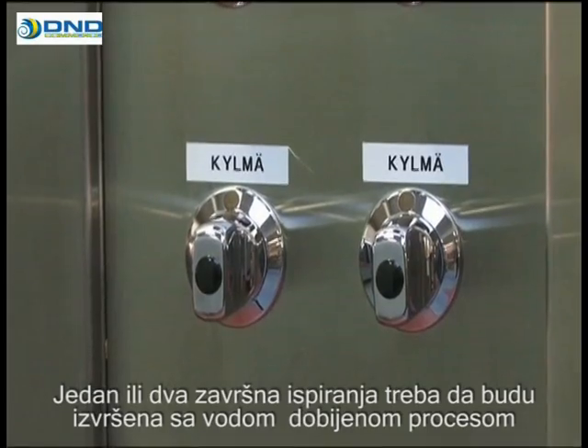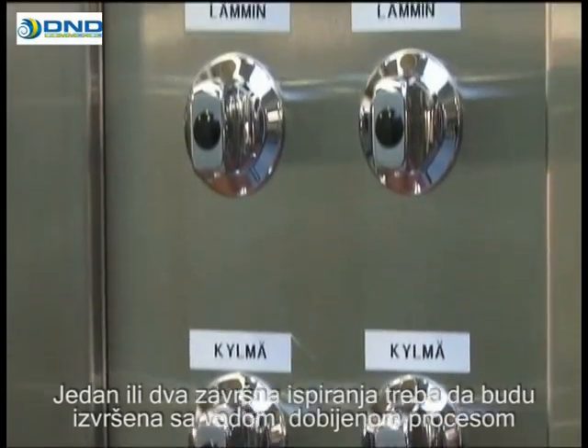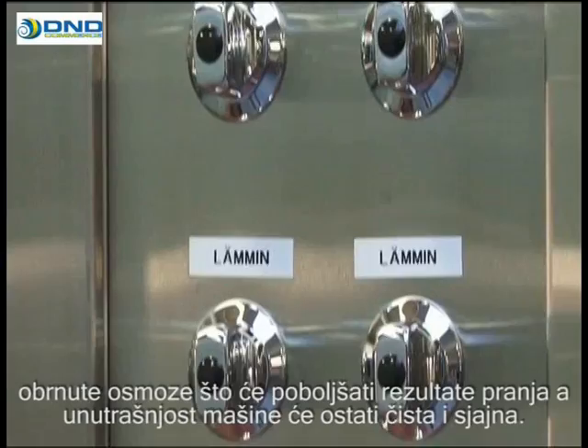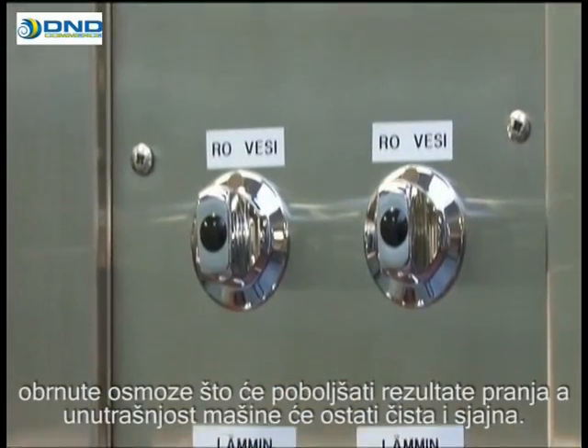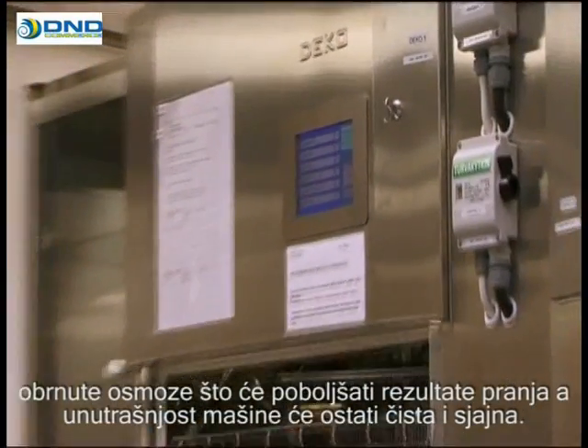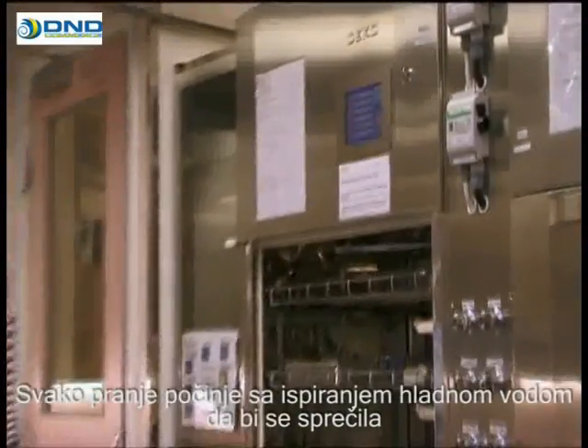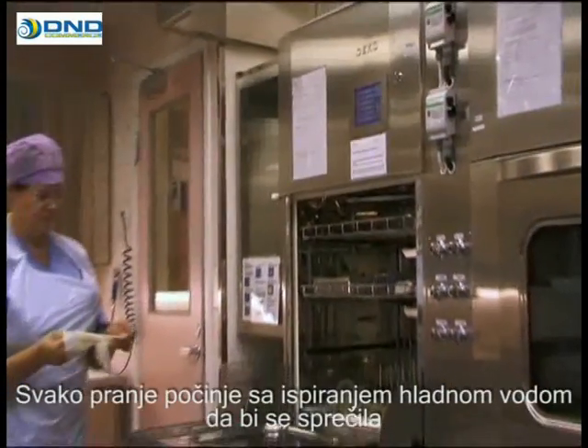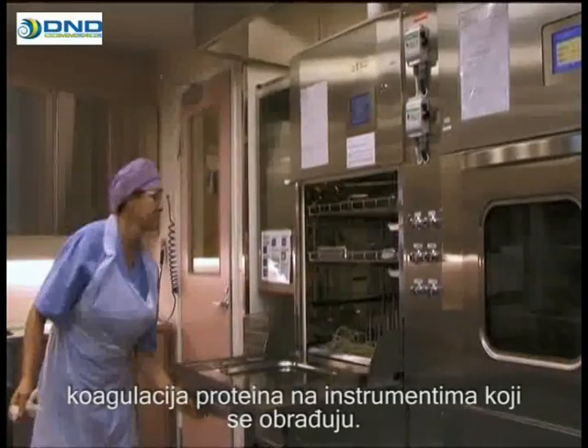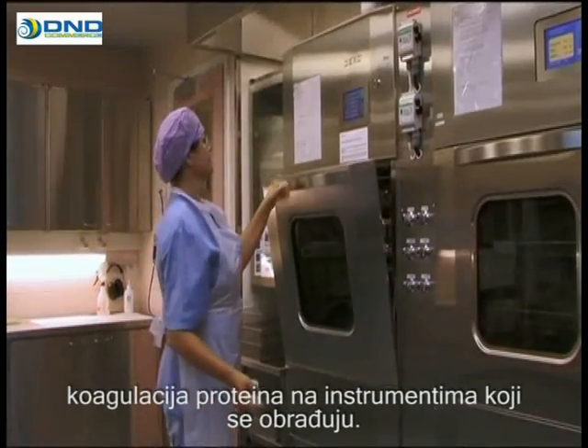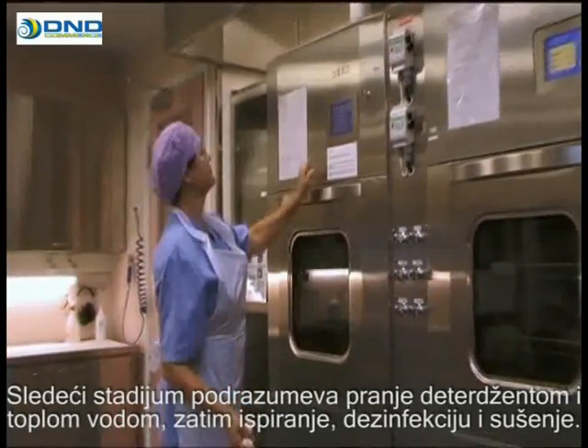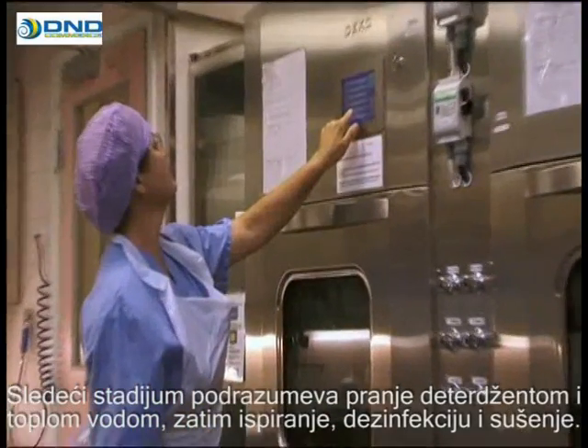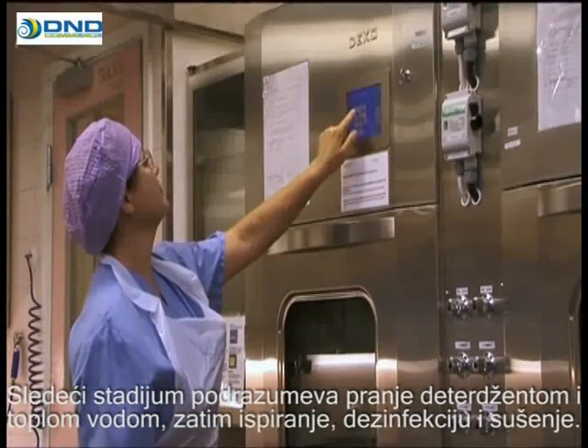One or two final rinses should be performed with RO water, produced with reverse osmosis equipment, making the rinse more effective and keeping the inside of the washer clean and shiny. Each wash begins with a cold water rinse to prevent proteins from coagulating on the processed instruments. The next stage involves washing with detergent and warm water, then a rinse, disinfection and drying.